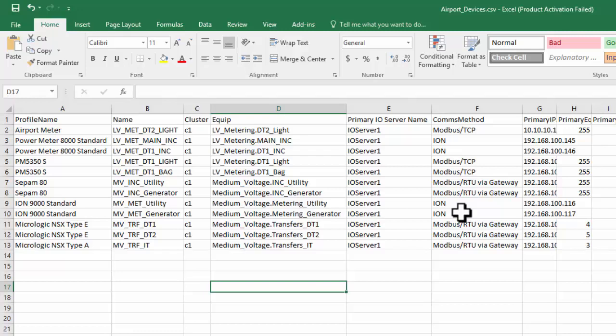That is to say, the Power Modbus driver can gather waveform data from compatible Schneider Electric Modbus devices like the CM4000, PM800, and MicroLogic Type H. However, this is not available to just any Modbus device, only those that the developers have enabled it for.